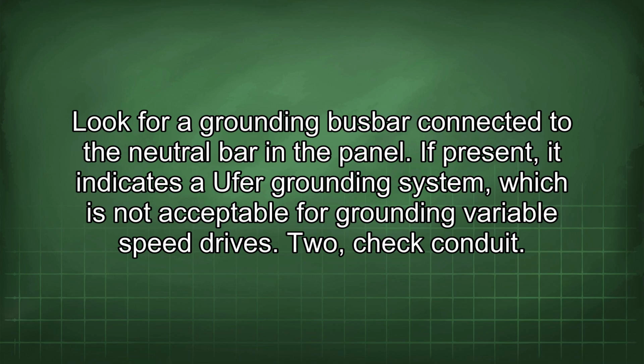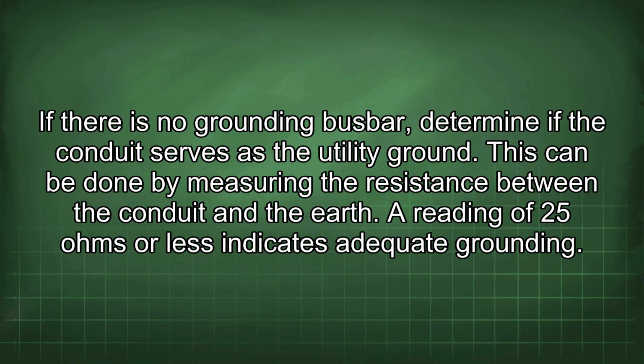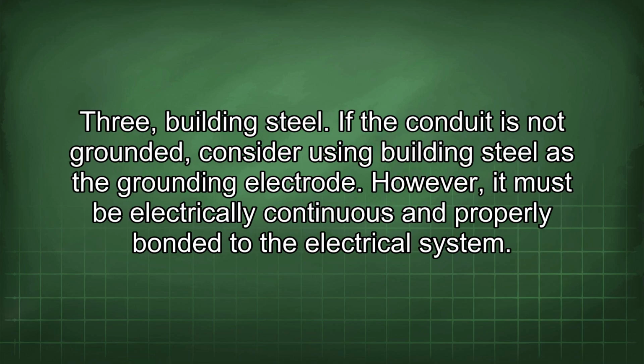2. Check conduit. If there is no grounding busbar, determine if the conduit serves as the utility ground. This can be done by measuring the resistance between the conduit and the earth. A reading of 25 ohms or less indicates adequate grounding. 3. Building steel. If the conduit is not grounded, consider using building steel as the grounding electrode. However, it must be electrically continuous and properly bonded to the electrical system.